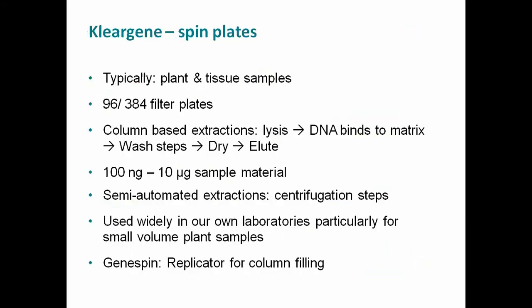The GeneSpin robot is a replicator platform able to fill Kleargene plates. Kleargene plates are typical column-based extractions you can use for plant and tissue samples. The big advantage enabling even higher throughput compared to Octopure is that you can use not only 96 filter plates but also 384 filter plates — processing four times more samples. As it's a column-based extraction, you follow the normal protocol: lysis, binding to a silica matrix in a column, several wash steps, drying to evaporate ethanol, and finally eluting the DNA. Sample yields are 100 nanograms to 10 micrograms.